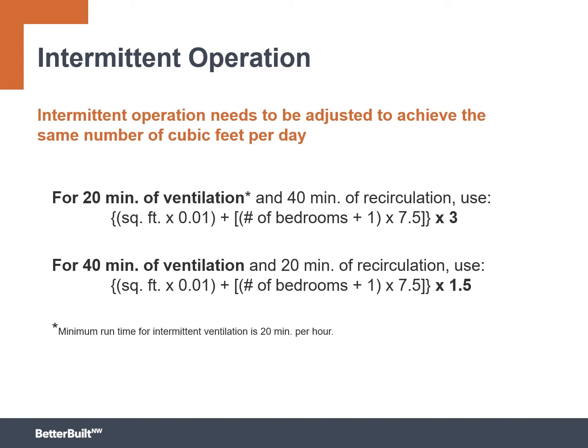Okay, so in this example, if we were going to run our HRV for 20 minutes out of every hour, then we would need to multiply that total by 3, right? Remember, 55 CFM was our minimum requirement. Now, all of a sudden, multiply that by 3, that's 165 CFM. That is a much larger heat recovery ventilator that you need to purchase to be able to do this work.